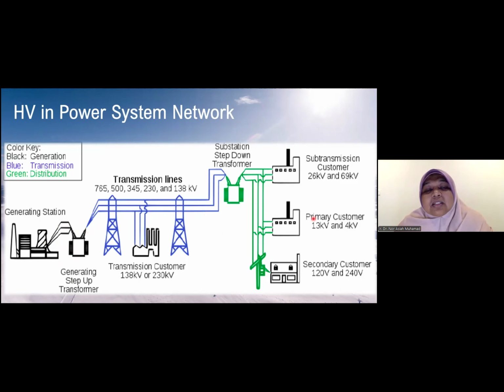The longer the transmission line to the customer, which means the longer the distance between the generation and the customer, the higher the voltage we require. This is because we need to transmit the same power with minimum loss of current. If we use high voltage, the current will be lesser, so we can reduce the loss in the transmission line. Then we have the substation, where we step down the voltage to the customer rated value.